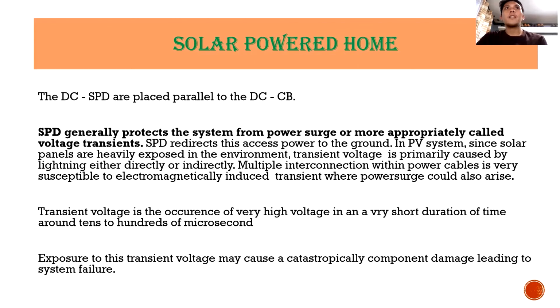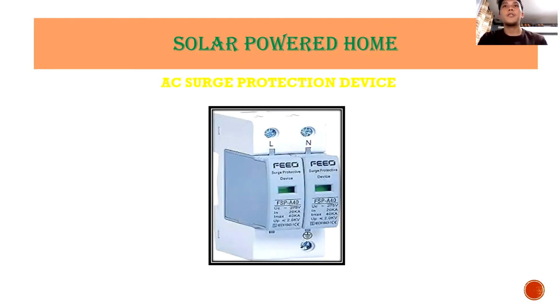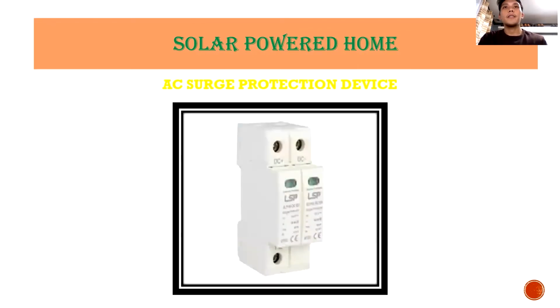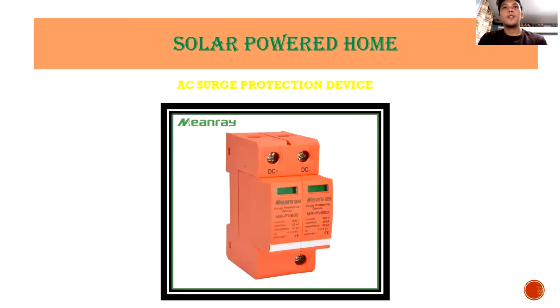So here we are tackling the electrical system's surge protection device, or the SPD. It is usually installed at the top of the configuration, parallel between the live conductors and the earth. The operating principle of the SPD is similar to that of the circuit breaker. In normal use, meaning no overvoltage, the surge protection device is similar to an open circuit breaker. But when there is an overvoltage, the surge protection device becomes active and discharges the lightning current to the earth. So this is an example of an AC surge protection device. This is another example, and here is another example too.